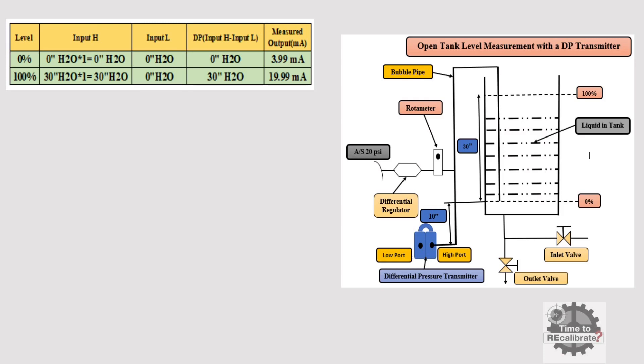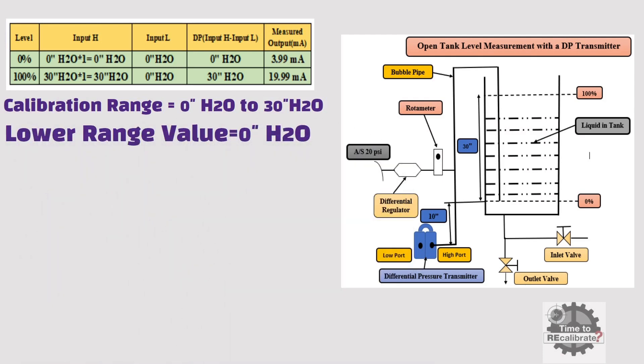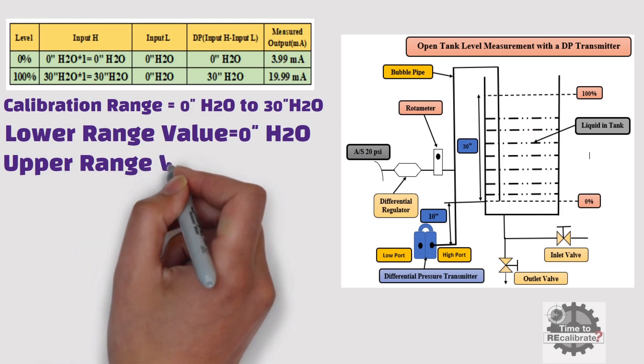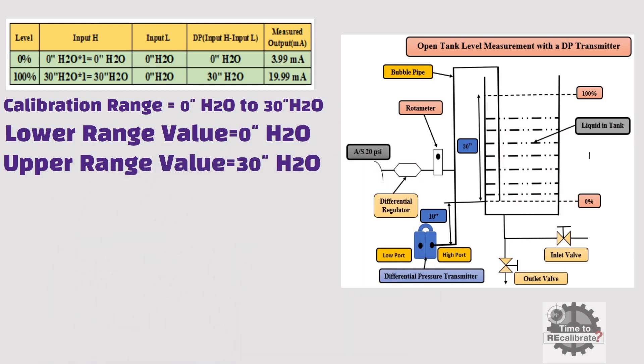Now let's understand the calculation for 100% level. At 100% level, the transmitter high side has 30 inch H2O pressure — 30 inches is the distance from 0% level to 100% level. The transmitter low side is open to air, so it has 0 inch H2O pressure at 100% level. Therefore, the differential pressure is 30 inch H2O at 100% level, and the calibration range is 0 inch H2O to 30 inch H2O. We have to set 0 inch H2O as the lower range value and 30 inch H2O as the upper range value in the DP transmitter using a HART communicator.